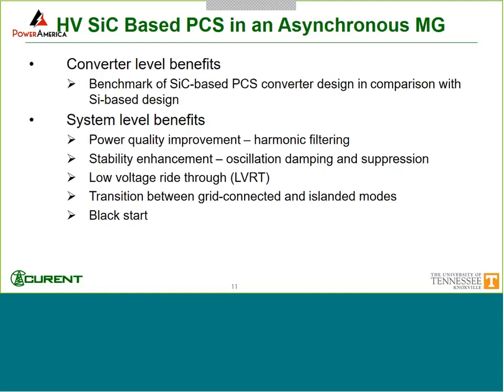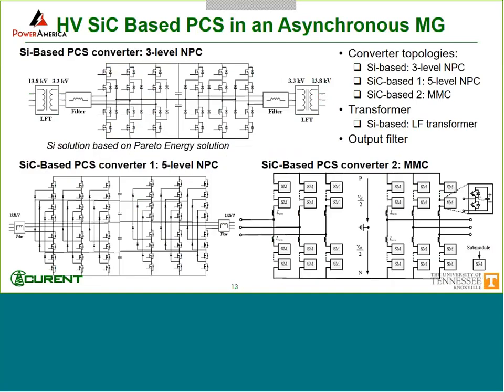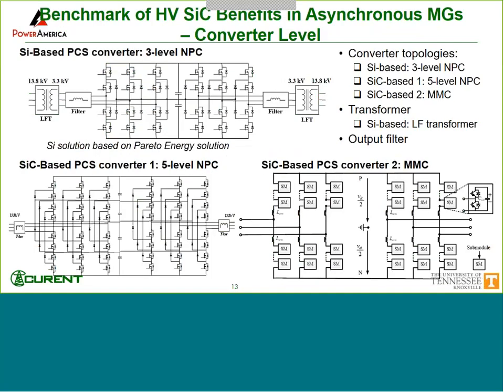The benefit can be grouped into two. First is at the converter level. We have conducted some benchmark of silicon carbide based PCS converter design in comparison with the silicon solution, the one I just showed you. And then the system level benefit includes the power quality improvement, like the harmonic filtering, stability enhancement, oscillation damping, and low voltage ride through and transition between grid connected and islanded modes, and also the black start.